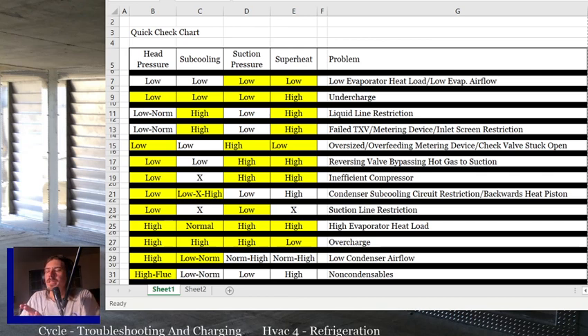The thing is, Carrier and Trane like to add discharge pressure. They like to add amps, and they like to add other stuff. Discharge pressure, amps, and then what's the other one? I think one of them adds discharge temp. They'll tell you what the discharge temp is or whatever, and I just never found it helpful. Nine times out of 10, this is all you need to troubleshoot it: head pressure, subcooling, suction pressure, superheat.